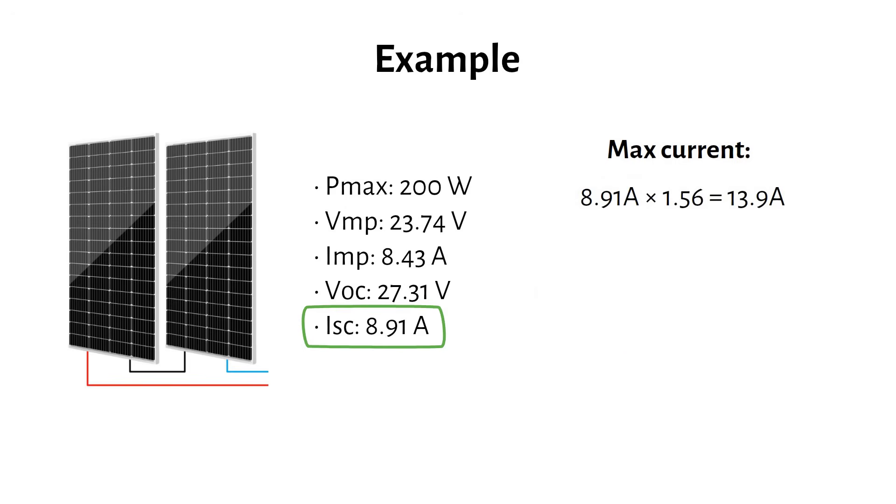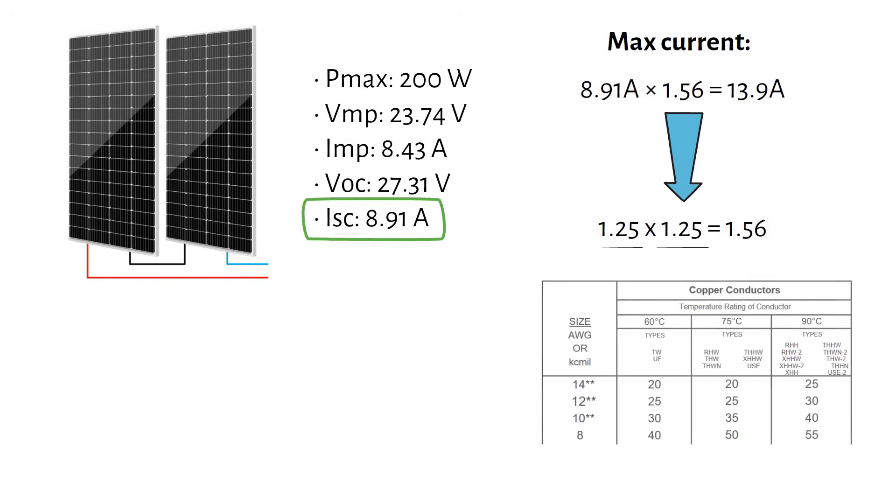That 1.56 factor is simply two safety margins stacked on top of each other. We are effectively derating the cable. The first is a standard for continuous current, and the second is for higher temperatures because the wire is exposed to direct sunshine. PV cable uses 90 degrees Celsius insulation.